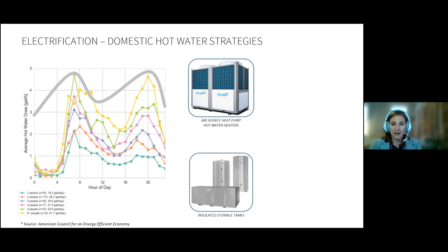Even though the system has capacity for the peak demand, the energy use is spread out over the course of the day and night, which helps to reduce overloading the grid during those peak times, avoids any peak surcharges, and also reduces demand on the electrical grid at times of peak electrical use, which tend to sort of coincide with these peak water loads also. So we become better grid citizens with this battery strategy.